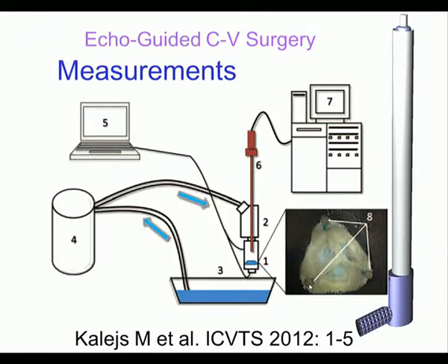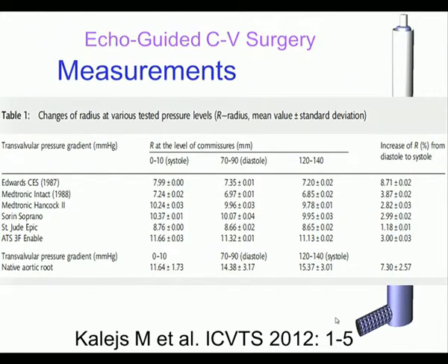You can see here a valve with ultrasonic crystals. The whole thing has to be put under water, and here we have an endoscope for visualization. We measure the pressure and have a system to load the valve with different pressures, and we can recuperate the overflow. The interesting thing to see is the last column which shows increase in radius in percent from diastole to systole. You can see all the valves tested and the native aortic root — pressurizing from 0 to 120 gives about 7% difference in stent post radius.